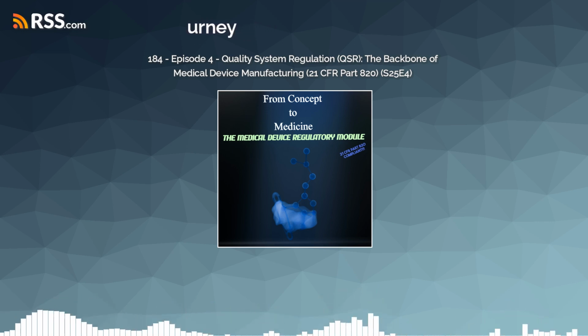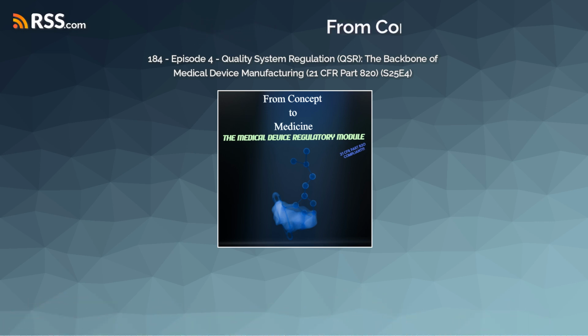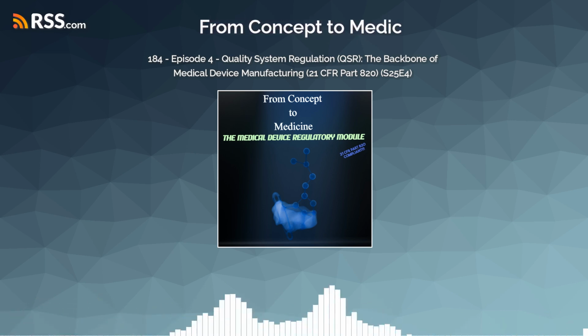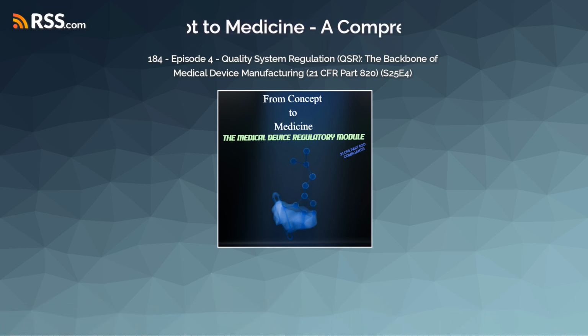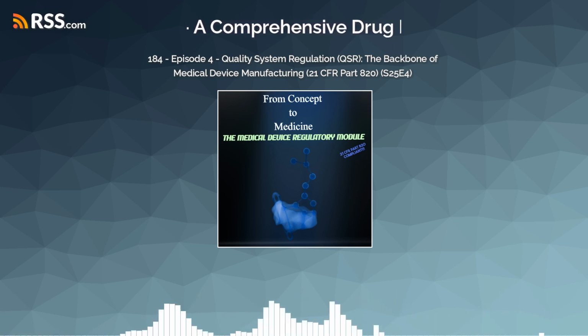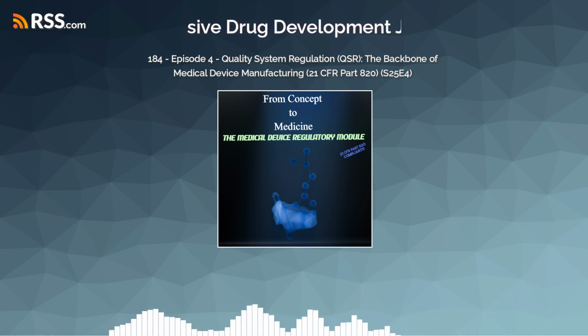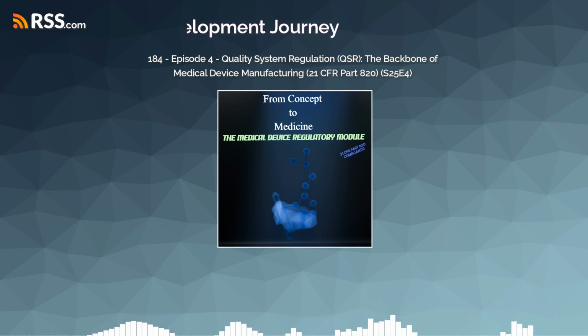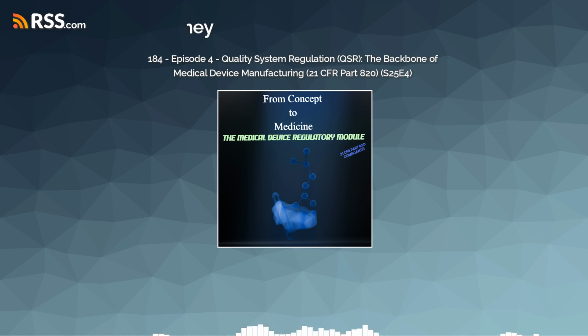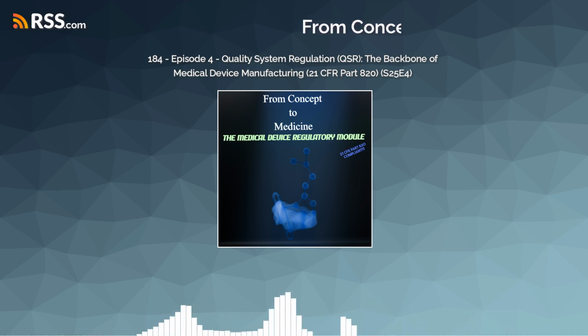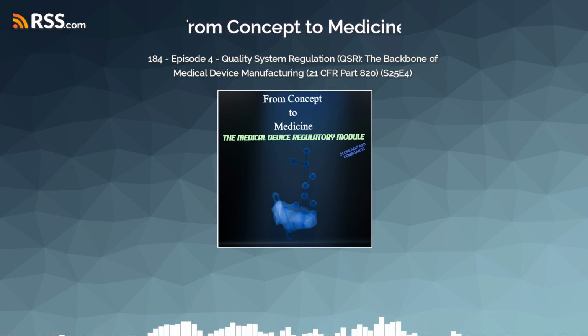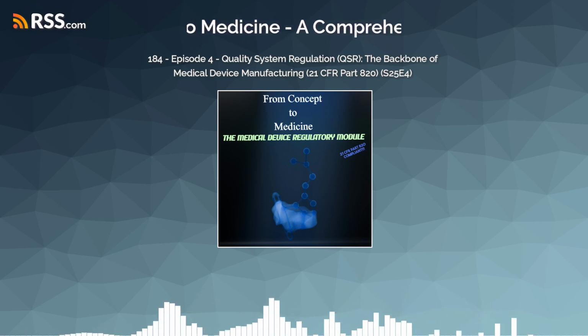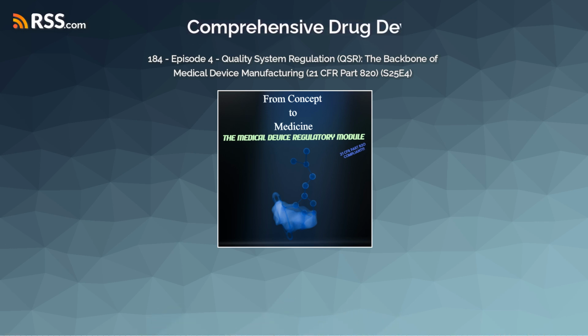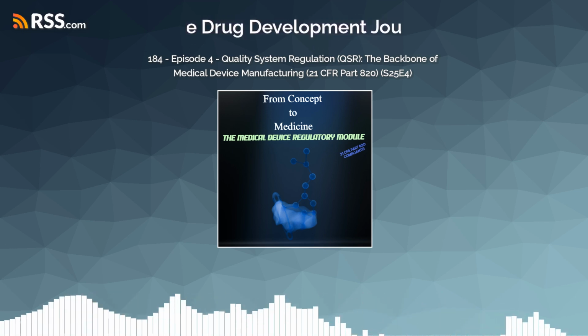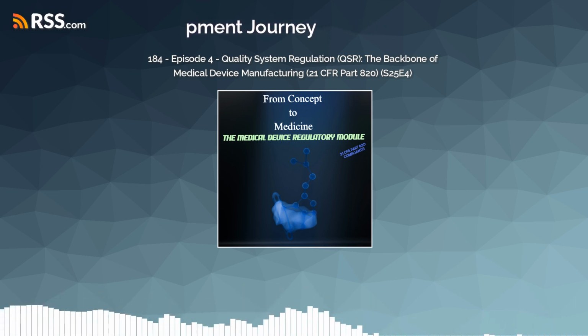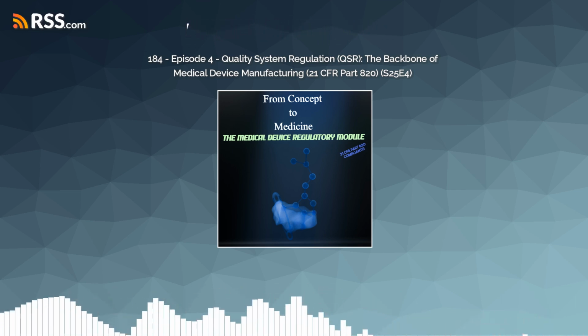Okay. Shifting back to the factory floor, production and process controls, let's talk equipment qualification. IQ, OQ, PQ sounds complex. It can be, but it's fundamental. Think of it in stages. DQ, design qualification. Is the equipment designed right for the job? IQ, installation qualification. Is it installed correctly according to the specs? OQ, operational qualification. Does it operate correctly across its defined range? Does it hit the right temperatures, speeds, pressures? And finally, PQ, performance qualification. Does it consistently produce good product under normal, real-world manufacturing conditions, often over multiple batches? So it's a progressive series of checks. Exactly. Rigorous proof that the equipment will consistently do what it's supposed to do day in, day out.